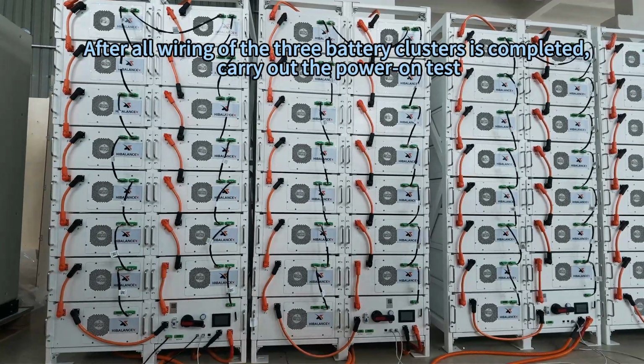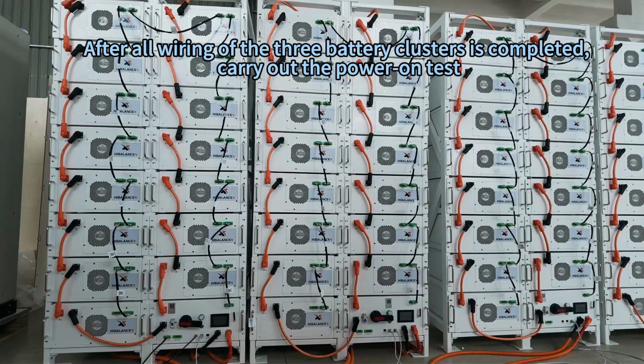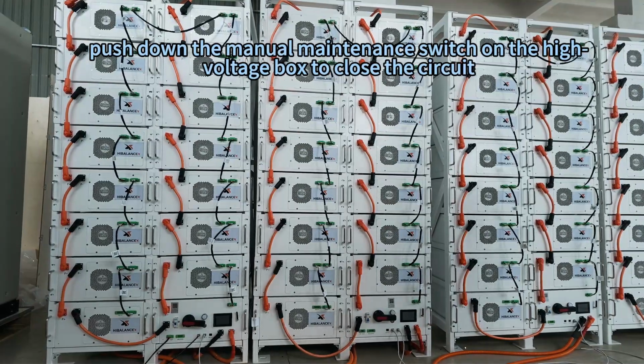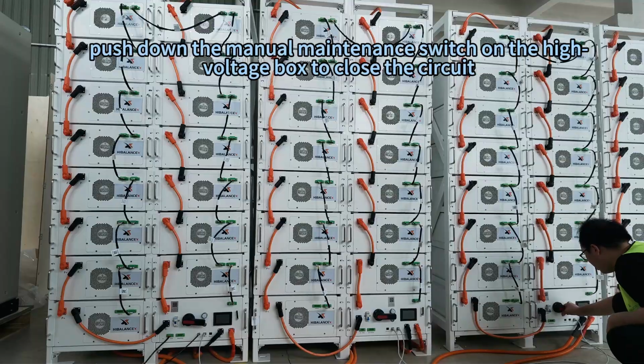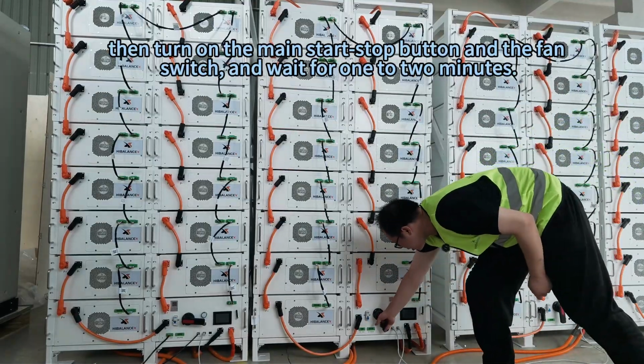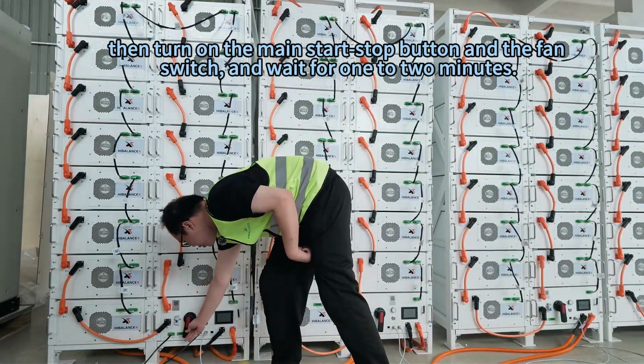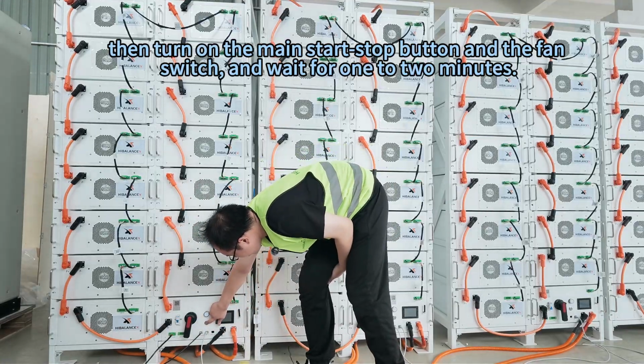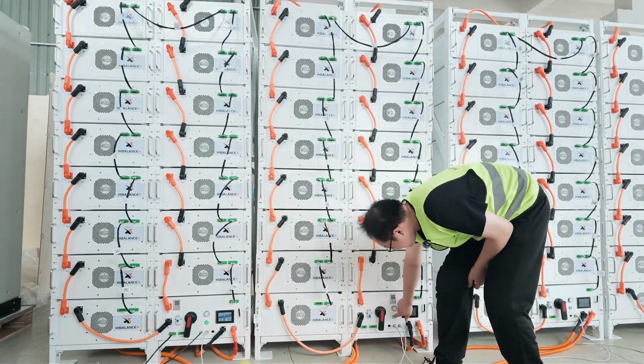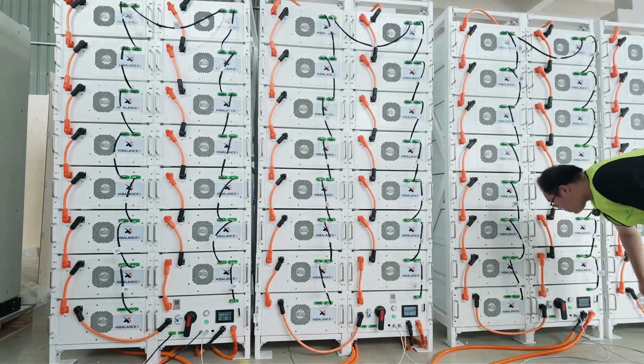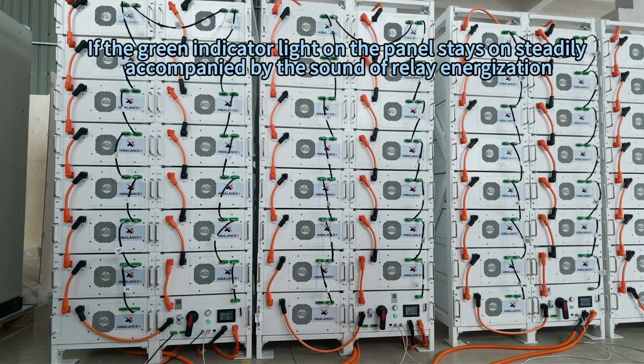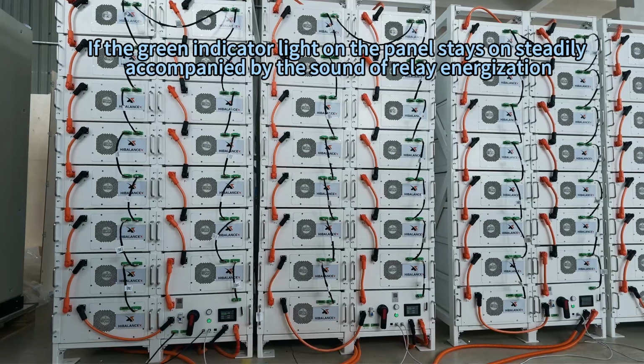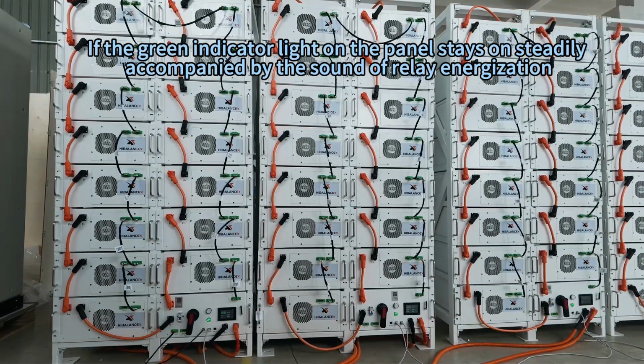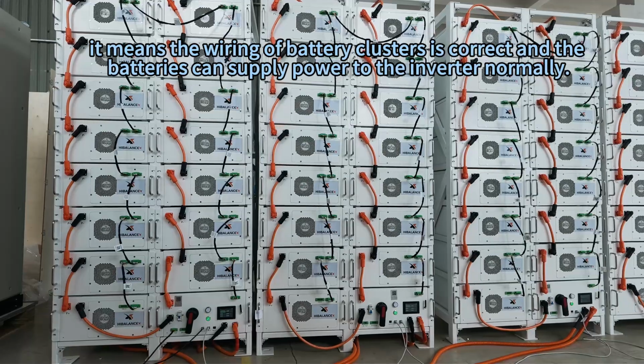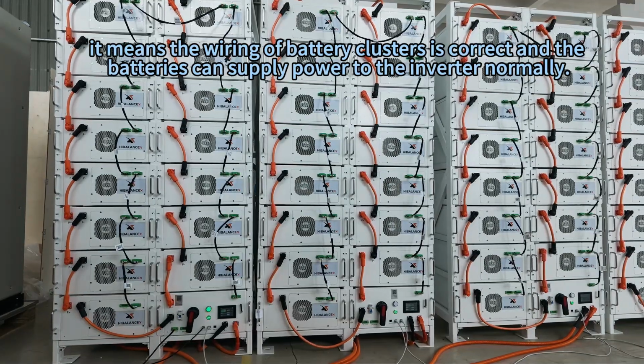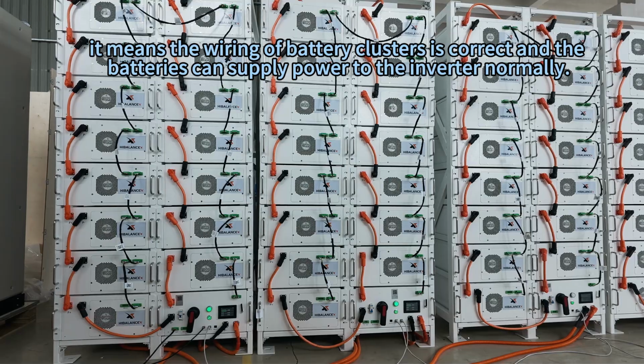After all wiring of the 3 battery clusters is completed, carry out the power on test. Push down the manual maintenance switch on the high voltage box to close the circuit, then turn on the main start-stop button and the fan switch and wait for 1 to 2 minutes. If the green indicator light on the panel stays on steadily accompanied by the sound of relay energization, it means the wiring of battery clusters is correct, and the batteries can supply power to the inverter normally.